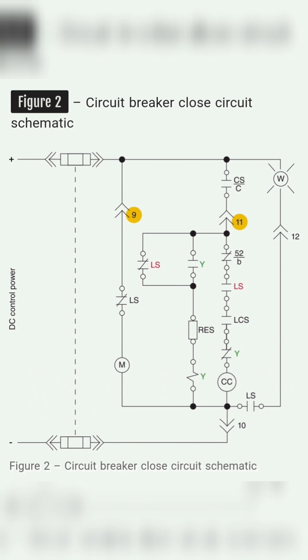Downstream of the latch check switch LCS is a normally closed contact from the anti-pump relay Y. The anti-pump relay Y acts as a one-shot device. As shown in Figure 2, the anti-pump relay is driven by the close signal on stab pin 11 and the position of the charging spring limit switch normally closed contact. Before the breaker is closed, the anti-pump relay is not yet energized as the charging spring limit switch is open. Once the breaker closes, the closing spring discharges, closing the normally closed charging motor limit switch LS, which energizes the anti-pump relay coil Y. The Y relay seals itself in with the Y relay normally open contact in parallel with the LS normally closed contact. The normally closed contact from the Y relay prevents the close coil from being re-energized until the anti-pump relay Y resets.